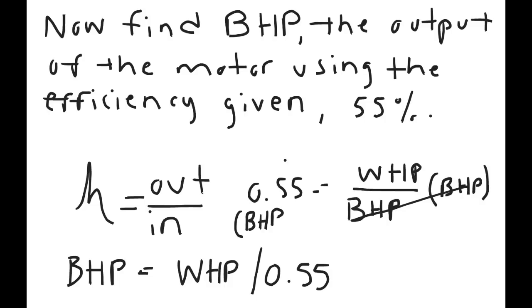That is, 0.55, the efficiency, 55%, is equal to the water horsepower over the brake horsepower. So when you set it up algebraically, it is brake horsepower equals water horsepower over 0.55.